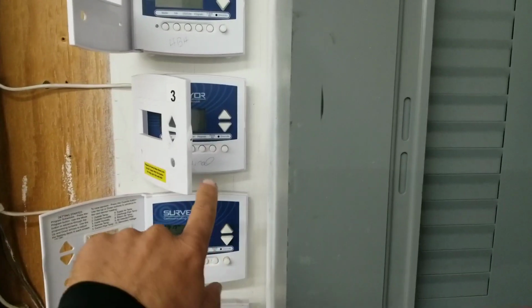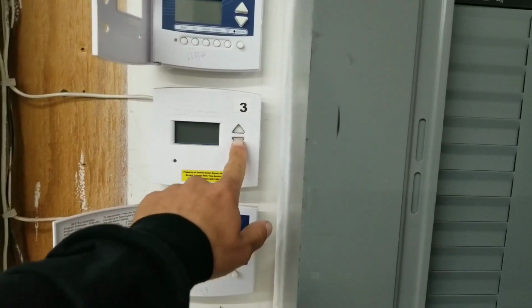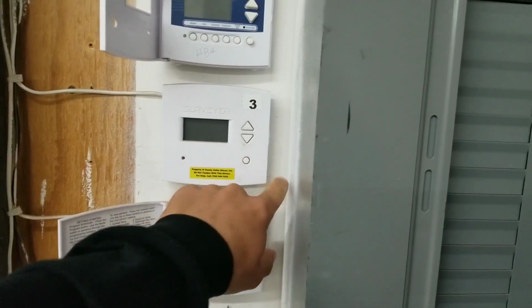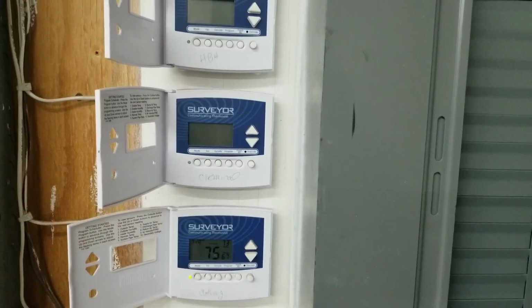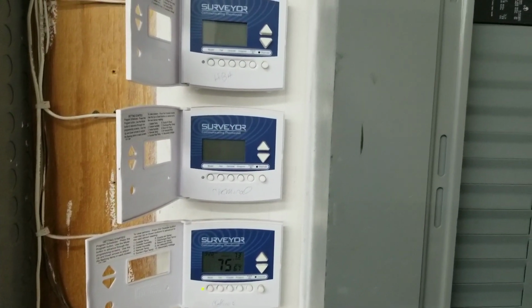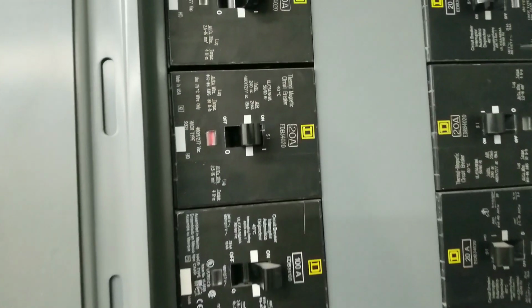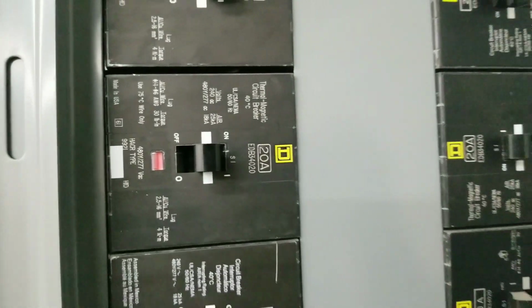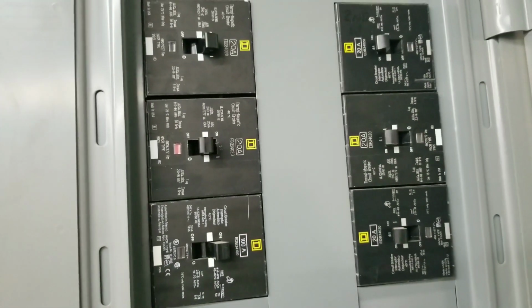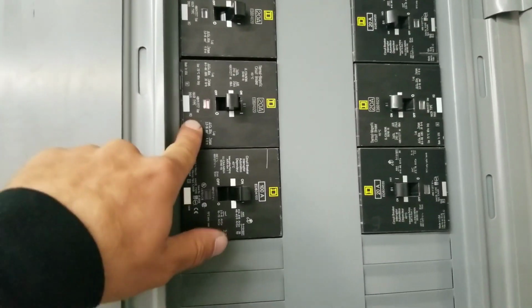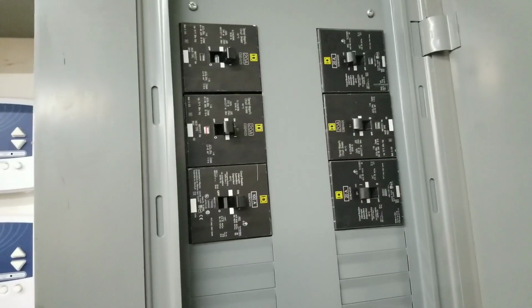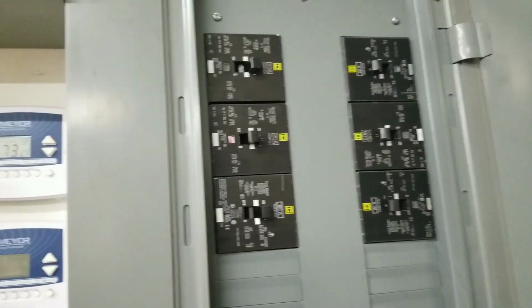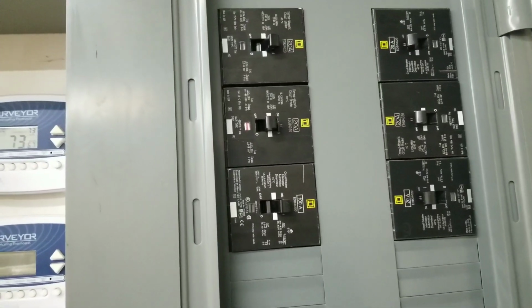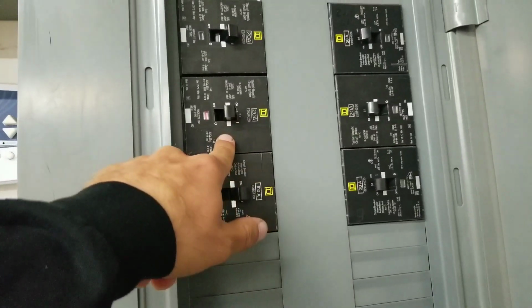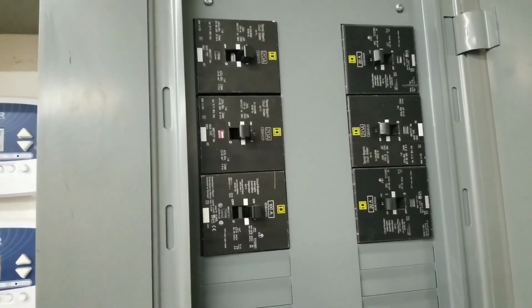Alright guys, here's our project for today. Unit number 3. Thermostat is blank. We have no cooling or heating going on at this location. So, get right there. I'm going to take a wild guess that this is our number 3 breaker. So I'm going to get up on the roof, flip that disconnect down on the unit, and then I'll come back, reset this, and then we'll troubleshoot that unit.